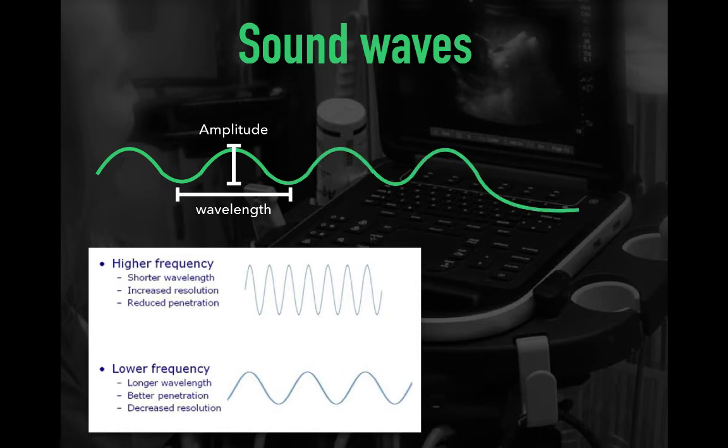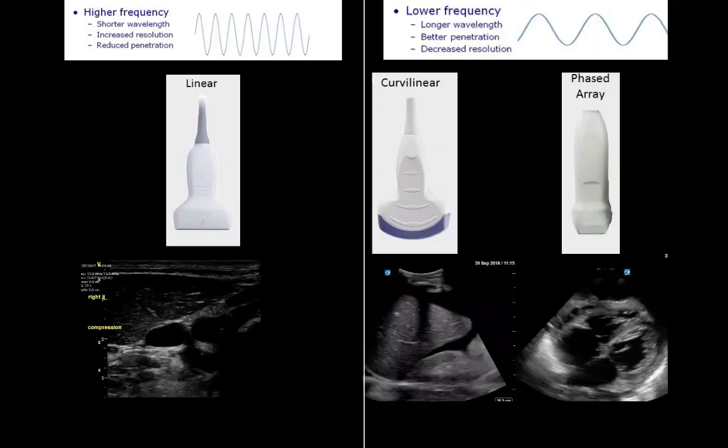Back to our sound waves. Ultrasound probes are designed to release a set frequency and wavelength — generally lower spectrum like 2 to 4 MHz, or high like 6 to 14 MHz, with the middle range in between. High-frequency shorter waves are great for superficial resolution but due to attenuation cannot penetrate deeply.